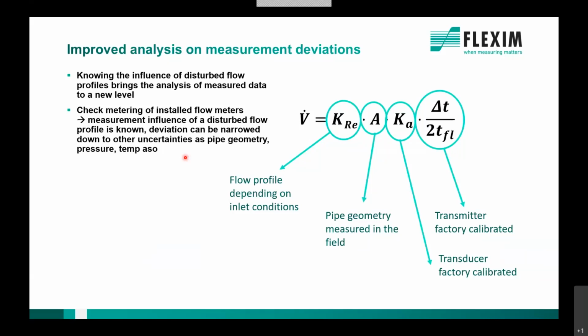And if you see a difference now to the meter you want to compare with, meaning if you use the FLEXIM meter as a check meter, then you know there is maybe a wrong reading of the meter you compare with. That's what we basically can state. Or maybe the pipe isn't that well known. You measure the circumference, well, that's okay. You measure the pipe wall thickness, that's also quite sure, and you can make sure that is correct. But what about build-ups? Some diagnostics might tell you that there is a build-up or some influences in the pipe wall, but if you still see a high reading, you may need to consider that you may have build-ups, and that is something you can narrow down.